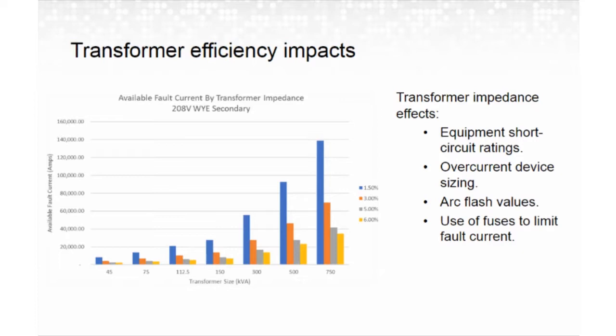As expected, lower impedances have higher available fault currents, and thus higher available fault currents affect the short circuit rating, or SCCR, of the electrical distribution equipment, and therefore increase cost as ratings increase. Additionally, we have arc flash and selective coordination that are impacted, and the designer needs to weigh all the costs associated with an electrical system when they're considering lower transformer impedances.